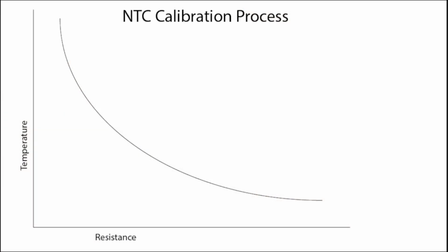To give you a better idea on how the controller is actually calibrating and how the mathematics is working behind the scenes, I've got a little graph here. So basically any NTC probe has a similar type of calibration process because the NTC probe is obviously not picking up temperature directly. It's basically picking up on a resistance and it's converting this to a temperature. And it does that using a sort of curve, something like this.